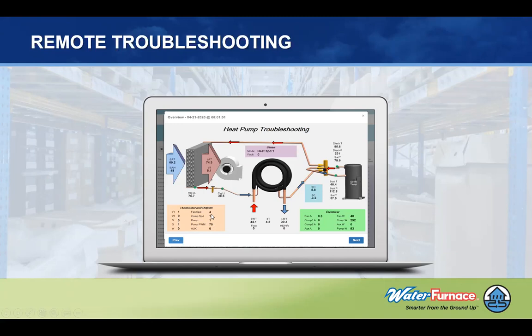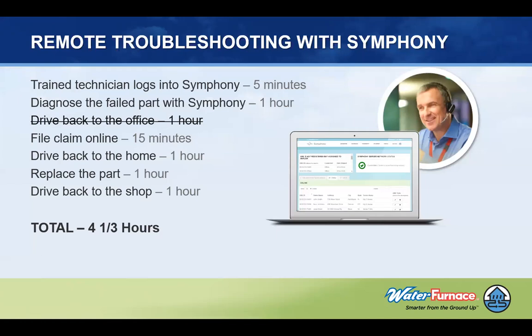And then finally, we know exactly what the thermostat is calling for and what speed we're supposed to be operating at, both from a fan and a compressor, to know if the call we're getting from the thermostat matches what the system is actually seeing from a performance standpoint. This really is what allows us to do the remote troubleshooting and diagnostics, because it's the same form that we've filled out for years on geothermal systems to get us to the level of certainty as to what's wrong. By doing this, we kind of changed the game on how we look at and troubleshoot a piece of equipment.